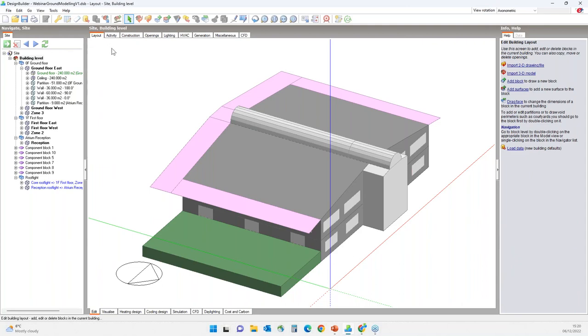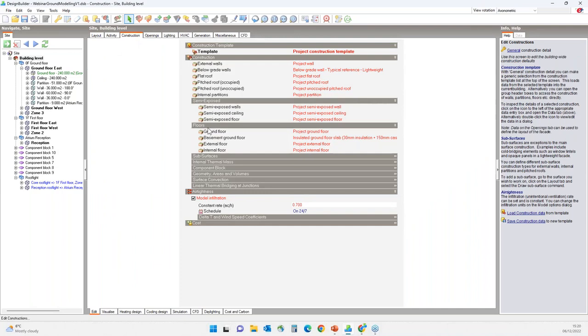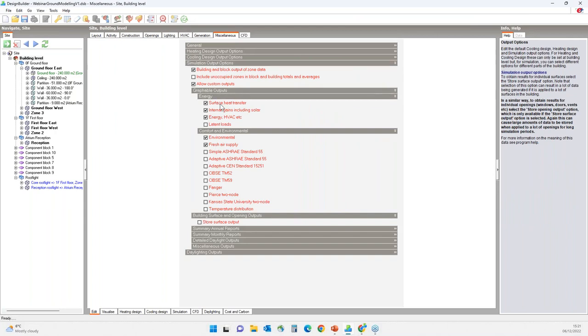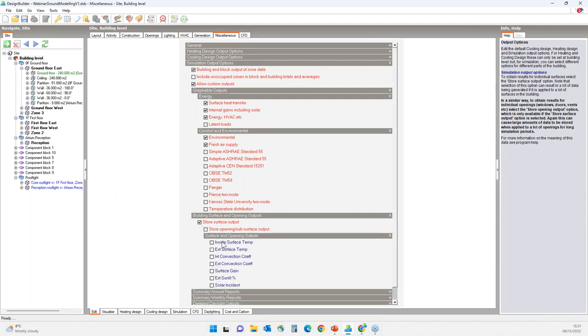Going back to the building level, another thing to keep in mind when modeling ground is to define the ground adjacent constructions correctly. On the constructions tab, ground floor, below-grade walls, and basement ground floor are typical ground adjacent constructions used in the model. As discussed earlier, it is generally best not to add earth layers to ground adjacent constructions. When assessing ground modeling results, it is useful to generate ground-specific results — on the miscellaneous tab in the simulation output options, you can select surface heat transfers to see how much heat transfer happens to the ground, and also store surface-level outputs such as inside surface temperatures.